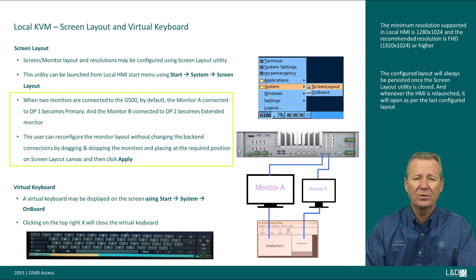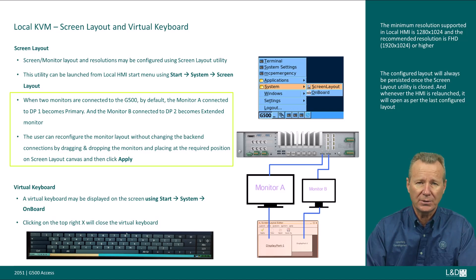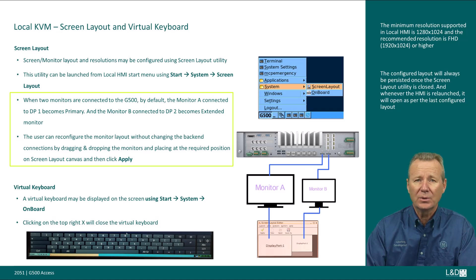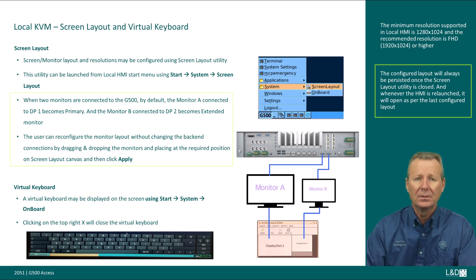Multiple monitors can be connected to the G500 via display ports. When a single monitor is connected, the connected monitor becomes the primary. When two monitors are connected, by default the monitor connected to the DisplayPort labeled DP1 becomes primary, and the monitor connected to DP2 becomes the extended monitor. Monitor A connected to DP1 is shown as DisplayPort 1 on the screen layout; monitor B connected to DP2 is shown as DisplayPort 0. The user can reconfigure the layout by dragging and dropping monitors on the canvas, clicking Apply, and closing the utility. The configured layout is always persisted and will be applied whenever the HMI is relaunched.